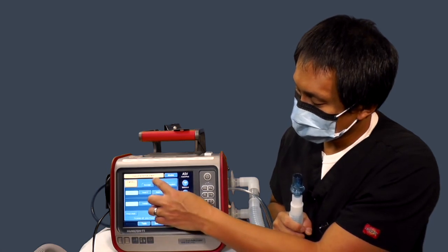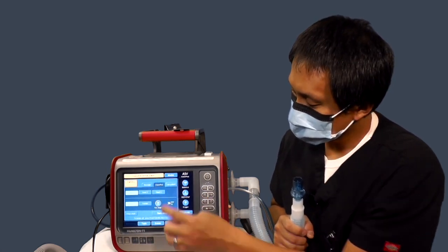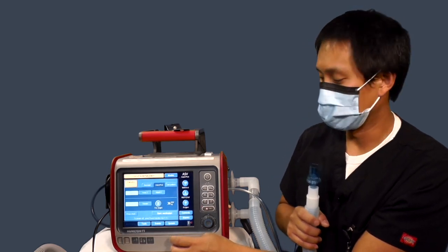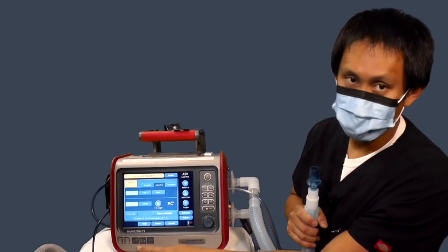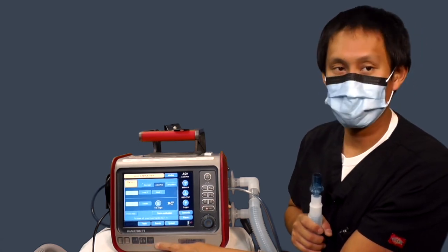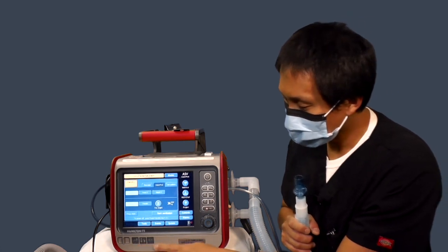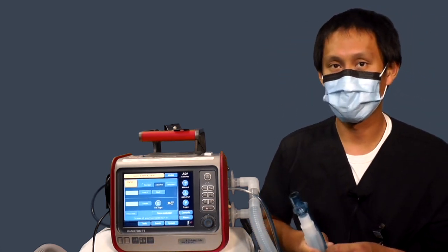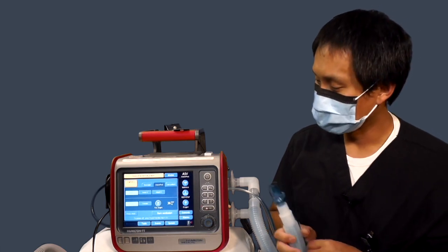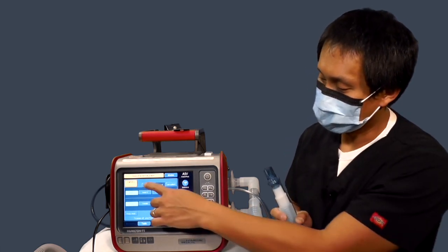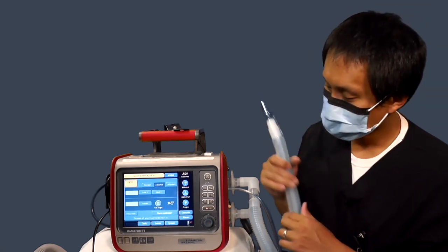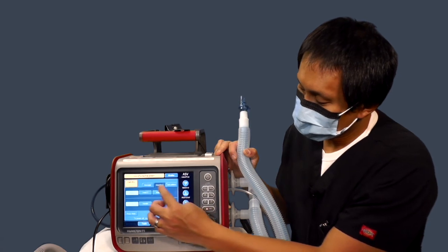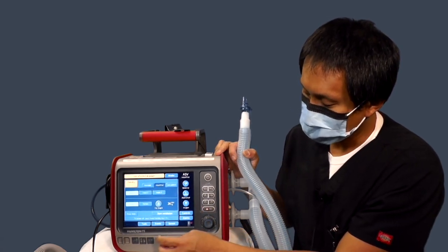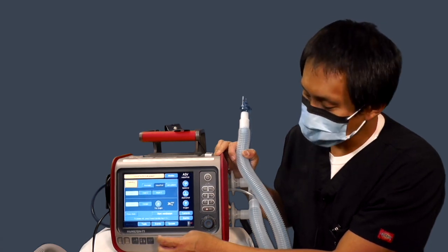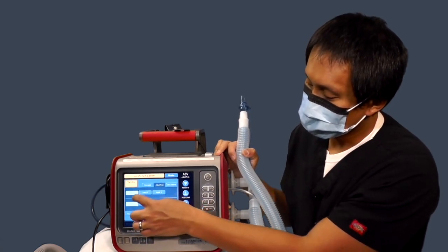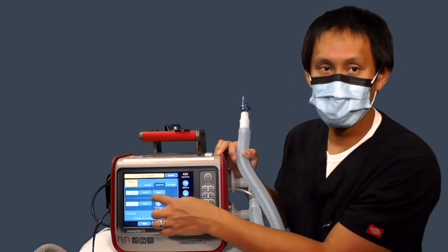This does have capabilities of neonatal, adult, and peds, depending on what your ventilator comes with. It'll have the corresponding stickers down at the bottom to let you know what's been preloaded on this ventilator. If your ventilator does not come preloaded with the neonatal feature, then the neonatal tab will not be there. Under adult peds, which most of the time Aircare Mobile Care will be using, it gives you 3 default presets. So you've got adult 1, 2, and 3.